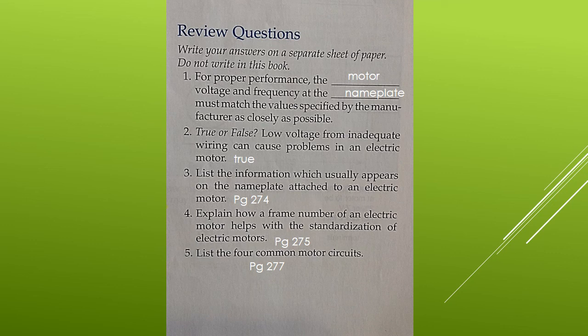Question 6, the NEC requires that the feeder capacity of a single motor circuit be 125% of the full load current rating of the motor. Question 7, what is the full load current of each of the following squirrel cage motors? For this, refer to tables in Article 430 of the NEC.